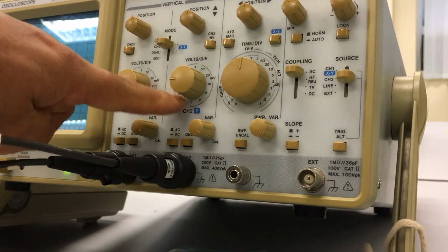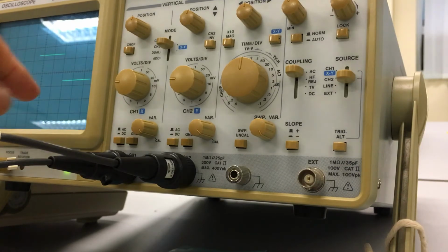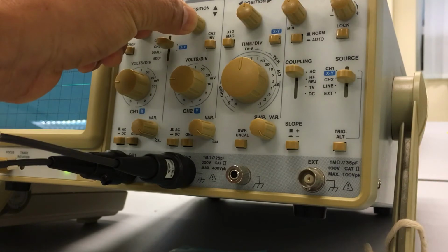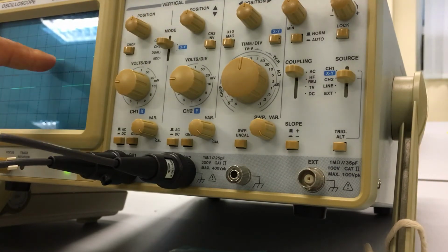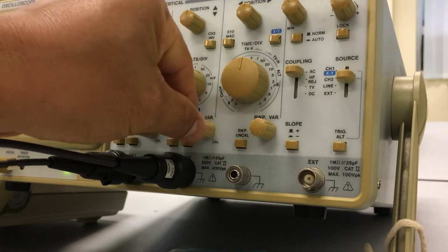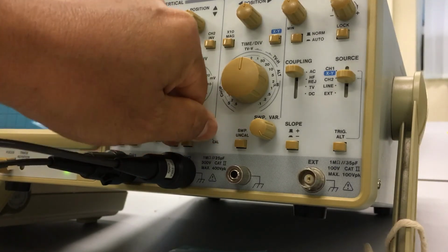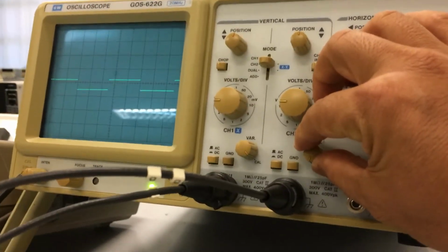So you select channel 2 now, 1 volt. It means that if 2 divisions are occupied by the square wave, you are going to get 2 volts peak to peak. You can use the position now, so you get 2 volts peak to peak. If you didn't get 2 volts peak to peak, you need to use the VAR button here to tune the voltage until you get 2 volts peak to peak. For example here, it's not 2 volts, right? So what you can do is tune this button, then you will get 2 volts peak to peak.